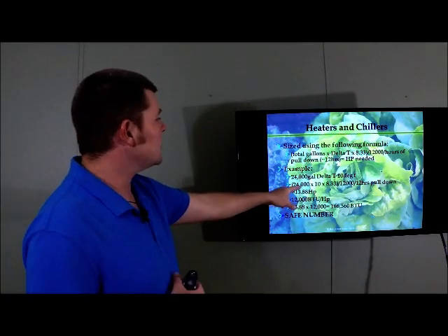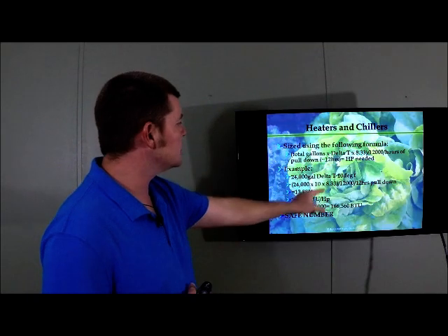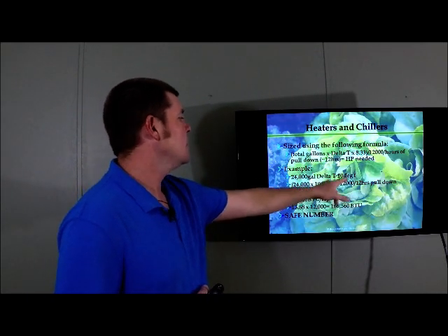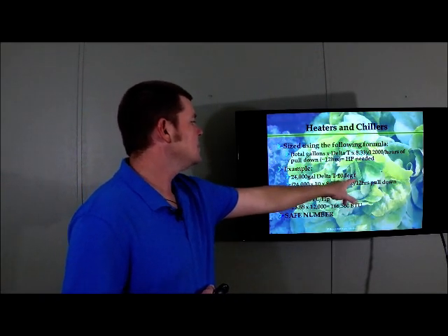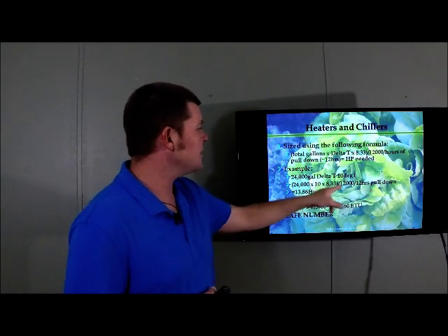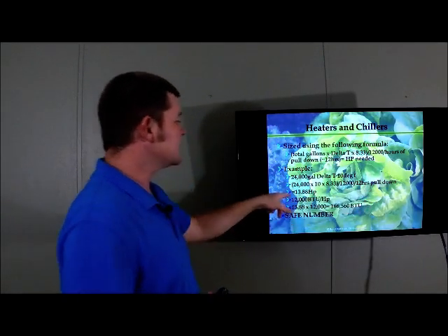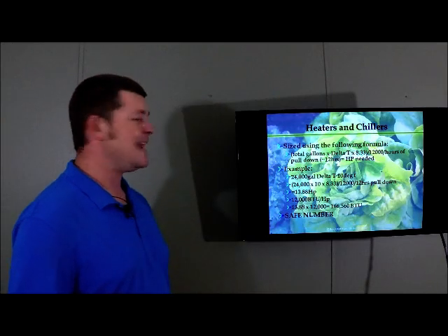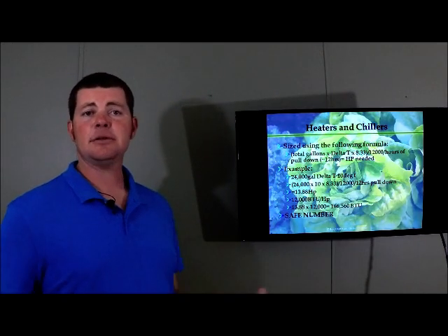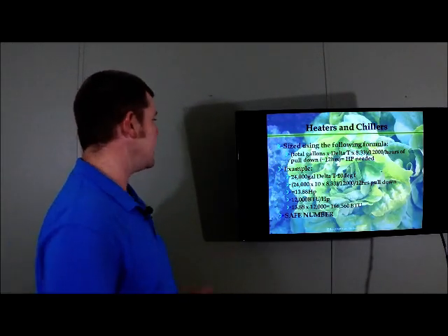So we do 24,000 times 10, which is our delta T, times 8.33, divided by 12,000, divided by 12 hours, okay? Given, given, given. This gives us 13.88 horsepower. We just calculated the chiller, just like a professional, okay? That's awesome.